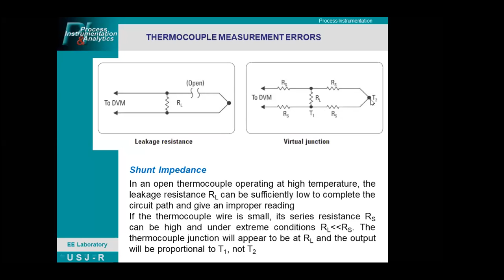So in an open thermocouple operating at high temperature, the leakage resistance may be sufficiently low to complete the circuit path and give an improper reading. If the thermocouple wire is small, its series resistance can be high, and under extreme conditions RL is less than the series resistance. So the thermocouple junction will appear to be at RL, and the output will be proportional to T1, not T2. Meaning what gets reflected is only this temperature T1, not T2, which is actually the source of the induced voltage produced by the thermocouple and the basis of the temperature at junction T2. So what it senses is T1, which is less than the temperature at junction T2.